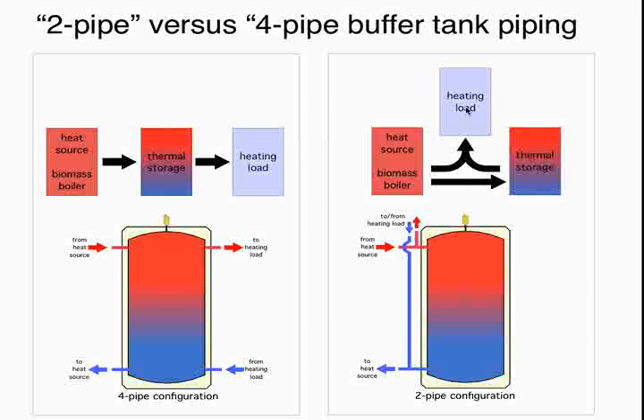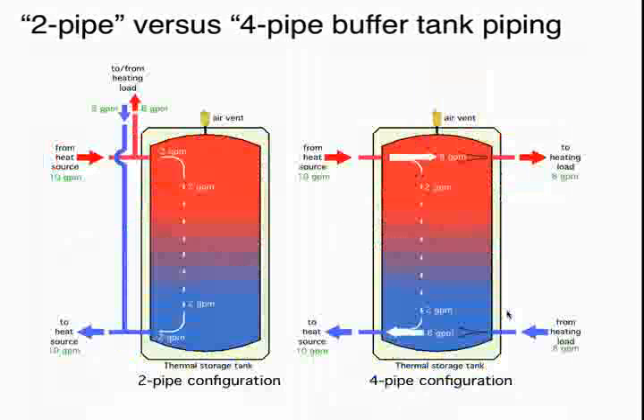All right? Let's say that the heat source is off and we have a very small heating load. At that point, we would be flowing backwards from thermal storage going to the heating load. And we can take heat back from the upper portion of this tank, go off to our load, and then return right back to the tank. So it's a nice configuration. I tend to like this two-pipe configuration. One of the reasons I like it is it reduces the flow velocity of the water going into the tank when we have a situation where the load is on and the heat source is on at the same time.